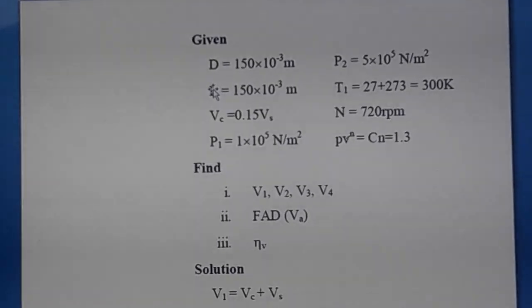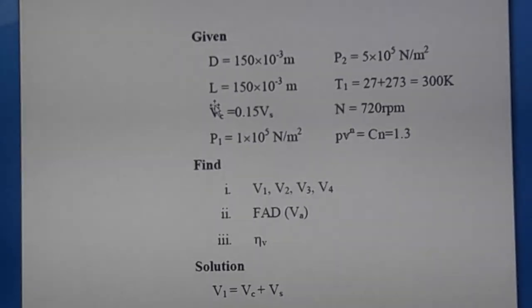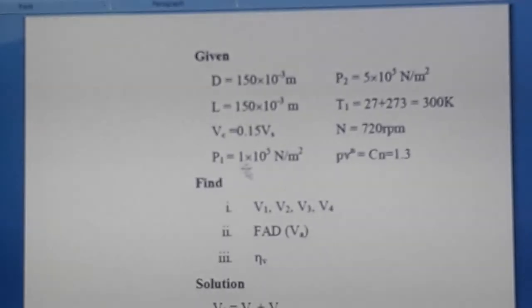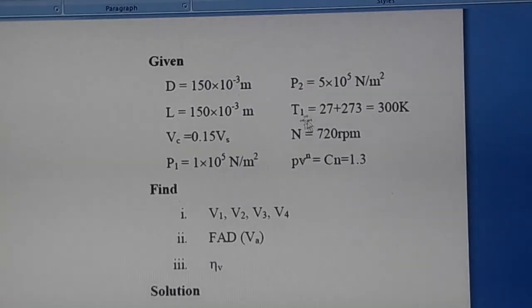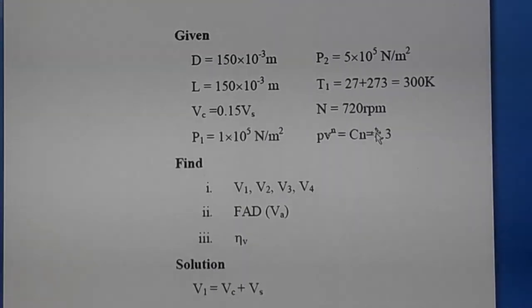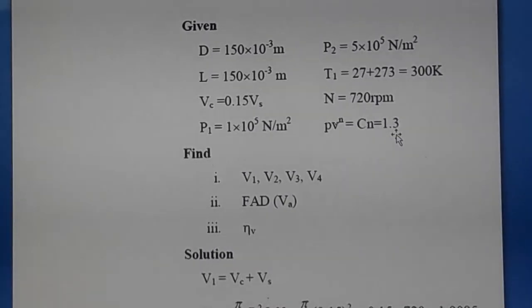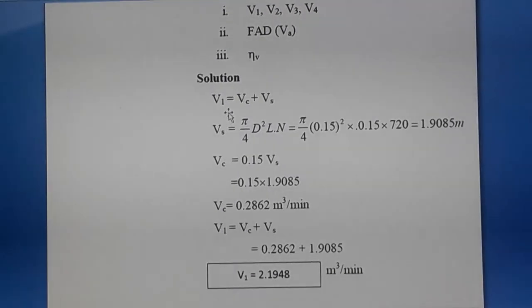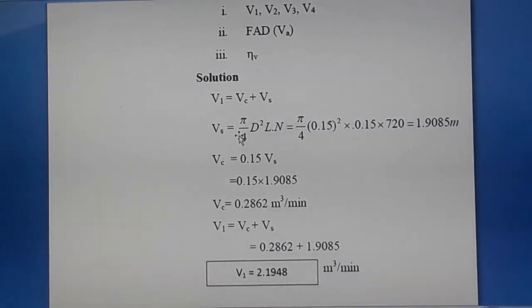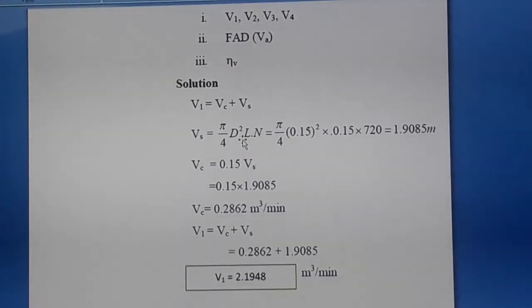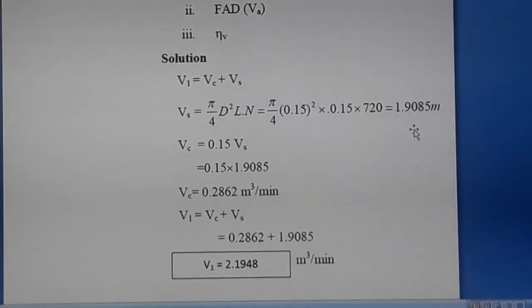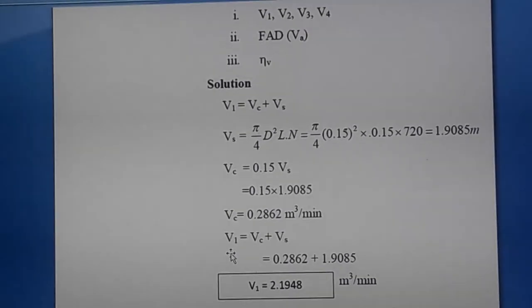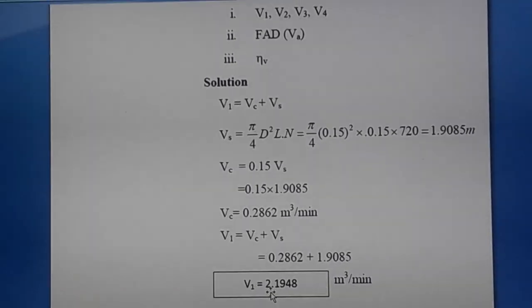Data: D = 150×10⁻³ m, L = 150×10⁻³ m, Vc = 0.15 × Vs, p1 = 1×10⁵ N/m², p2 = 5×10⁵ N/m², T1 = 300 K, N = 720 rpm, n = 1.3. Swept volume Vs = (π/4) × D² × L × N = 1.9085 m³/min. Clearance volume Vc = 0.15 × Vs = 0.2862 m³/min. Total volume V1 = Vc + Vs = 2.1948 m³/min.